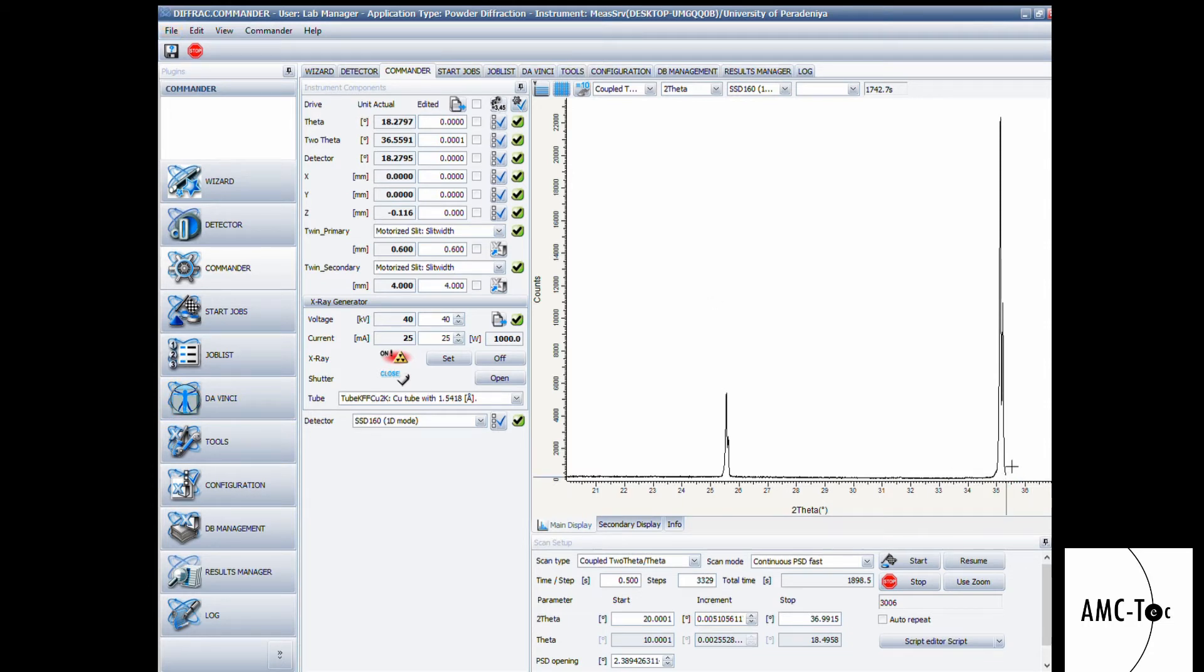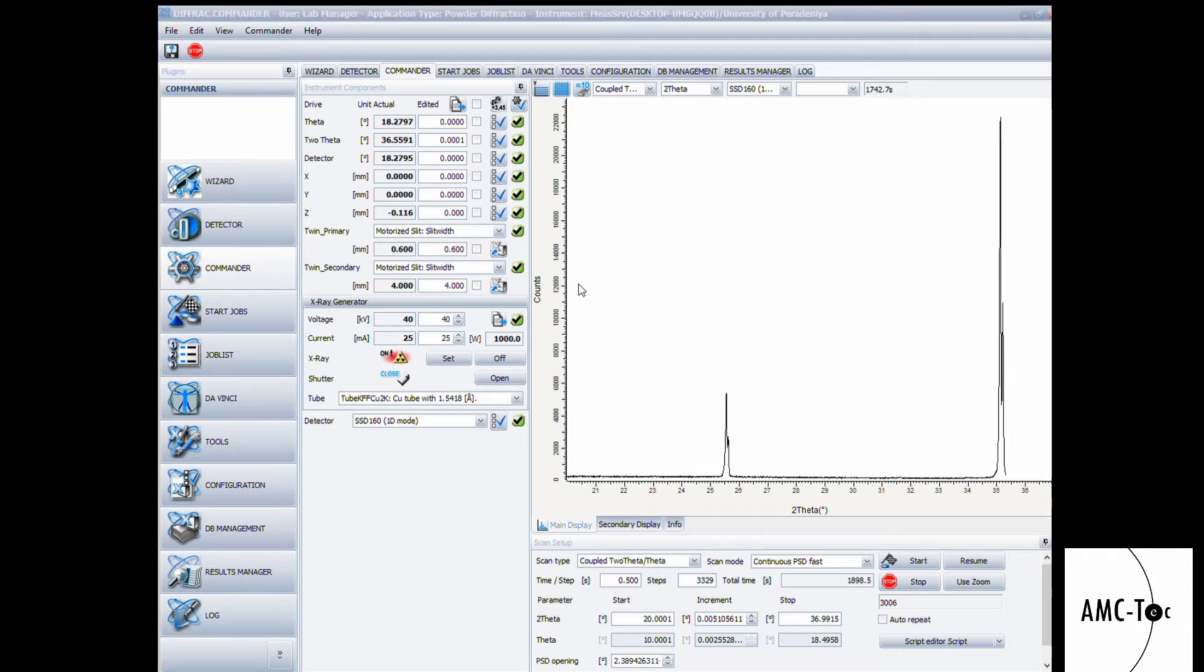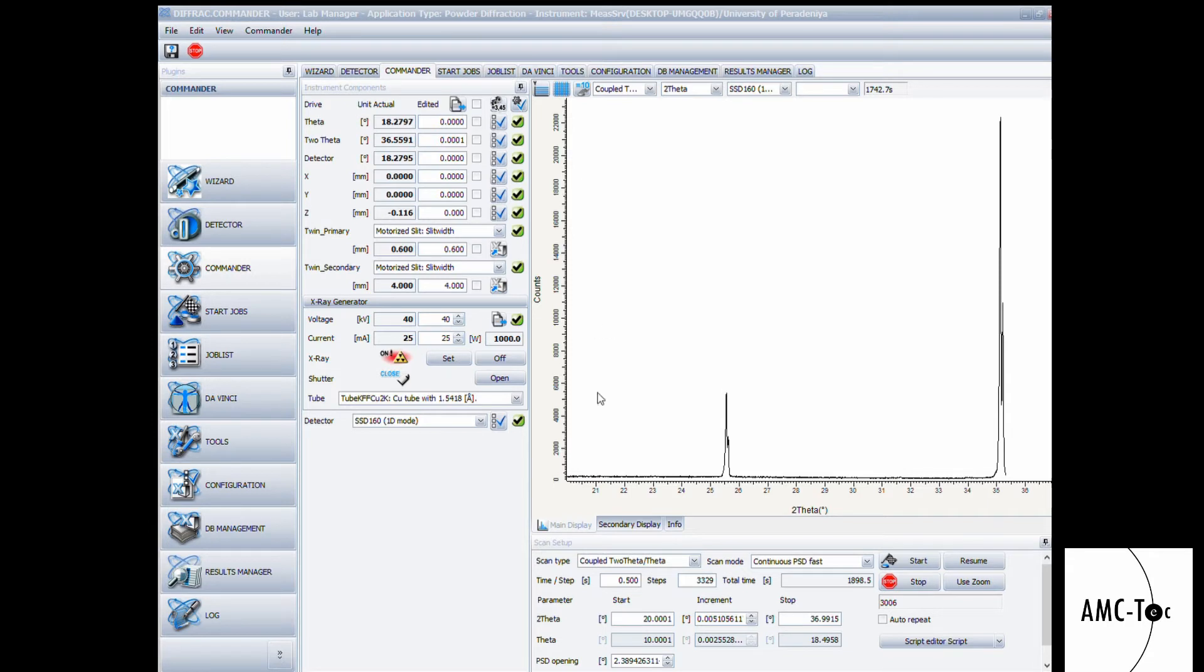This is the obtained diffractogram for the standard quartz calibration sample. Now we can do a peak fitting and check whether the peaks are shifted or not. If the peaks shifted, then we have to do a detector calibration. But for the purpose of this video, we will do a detector calibration even if it's not shifted.